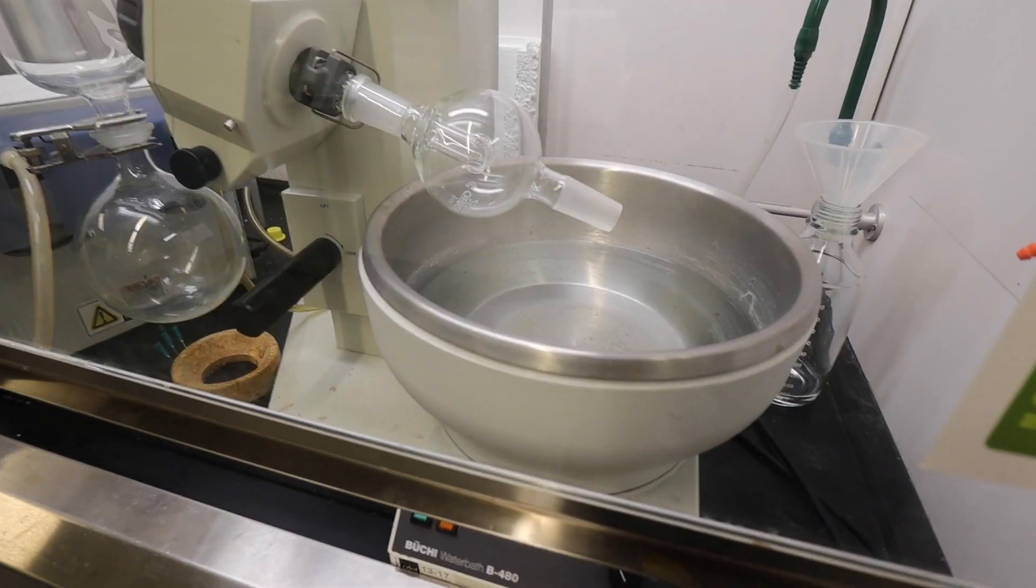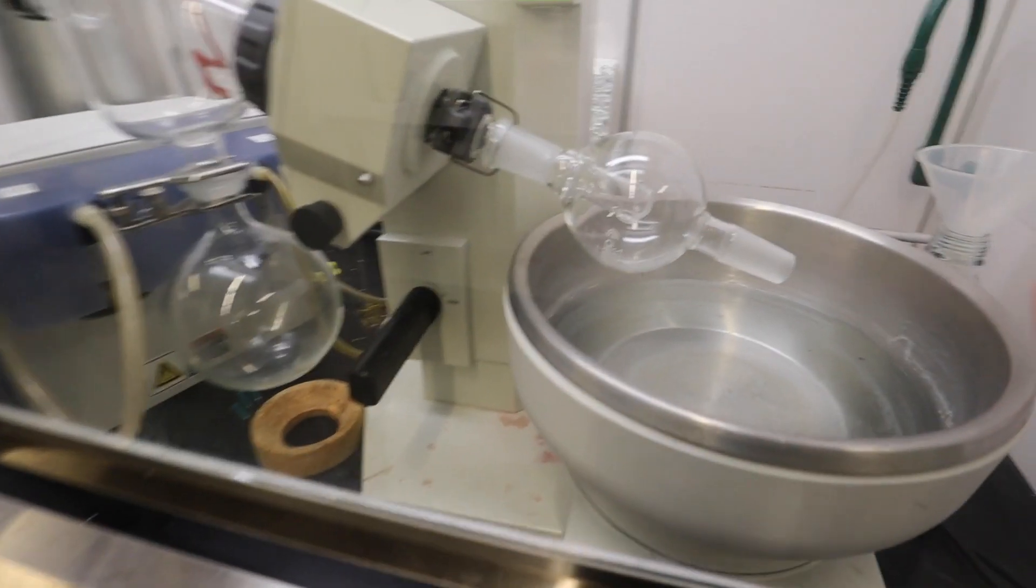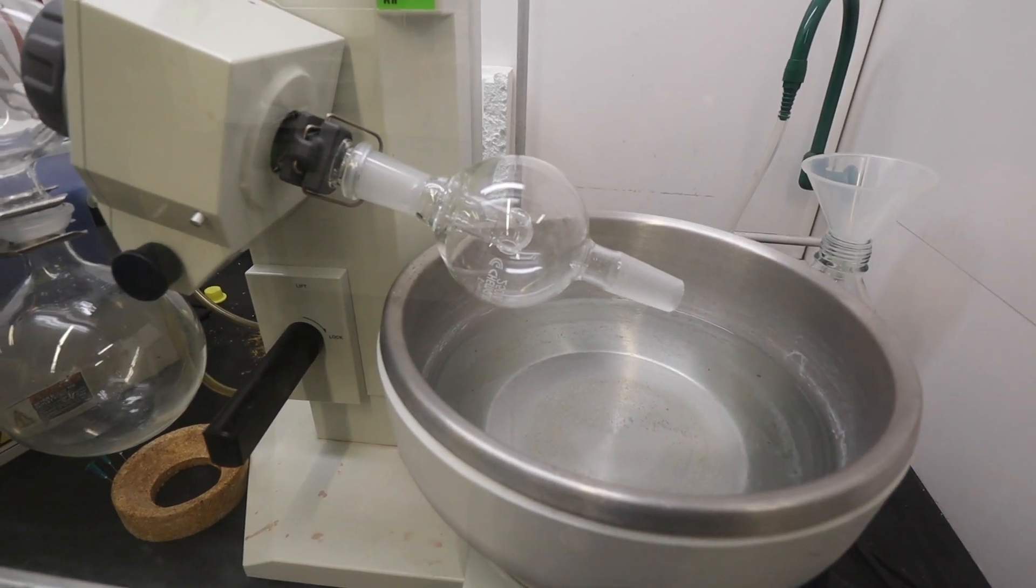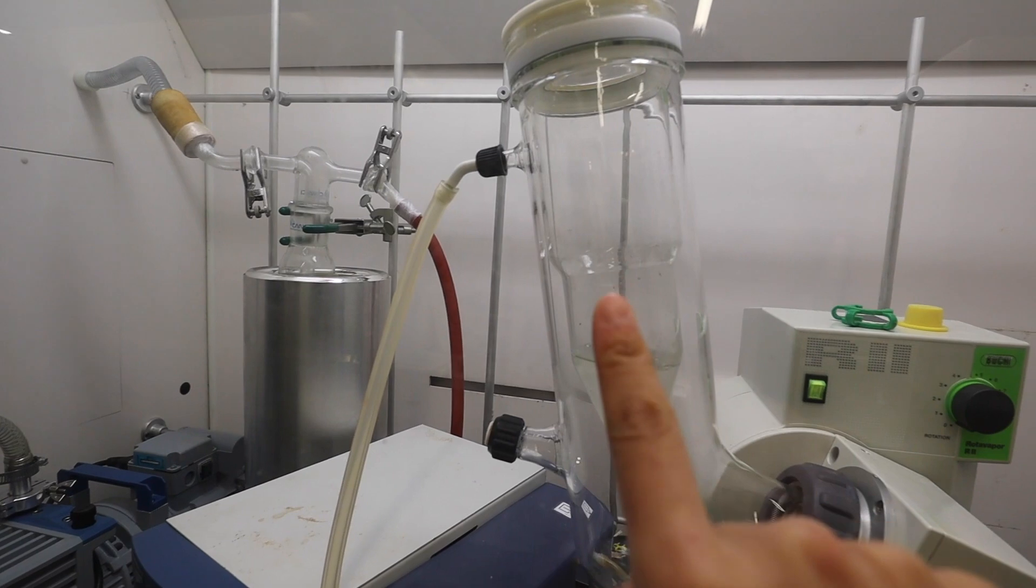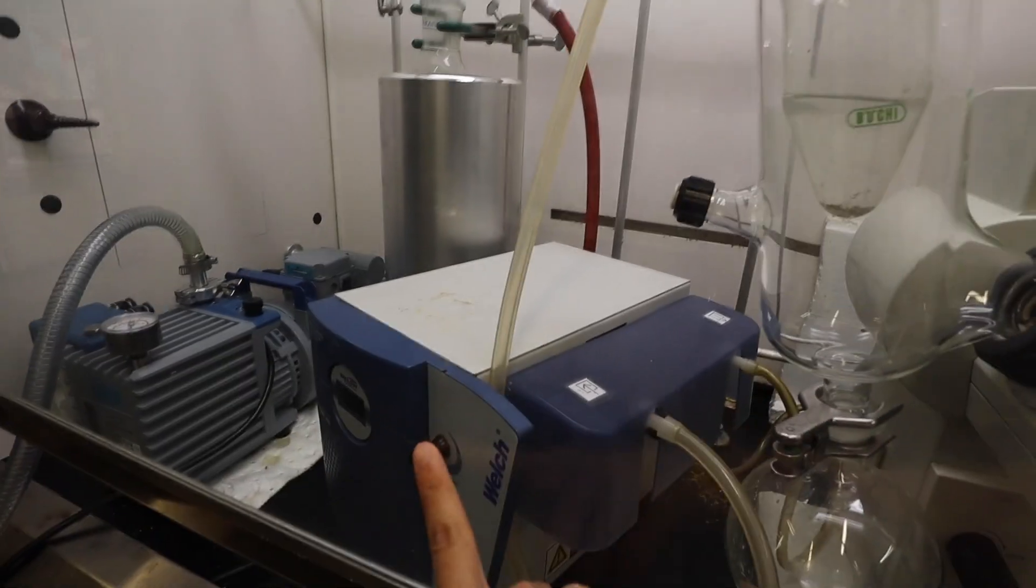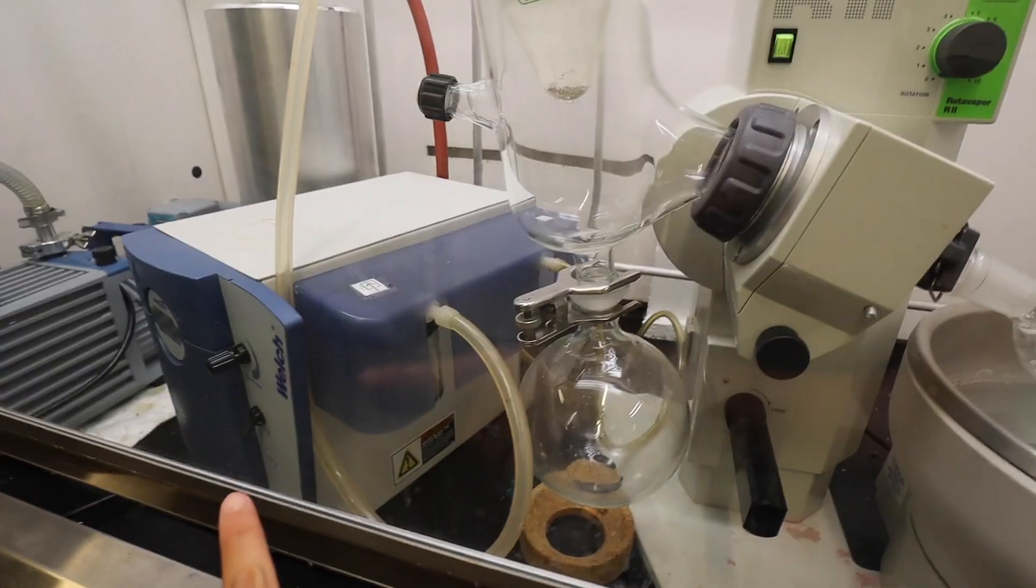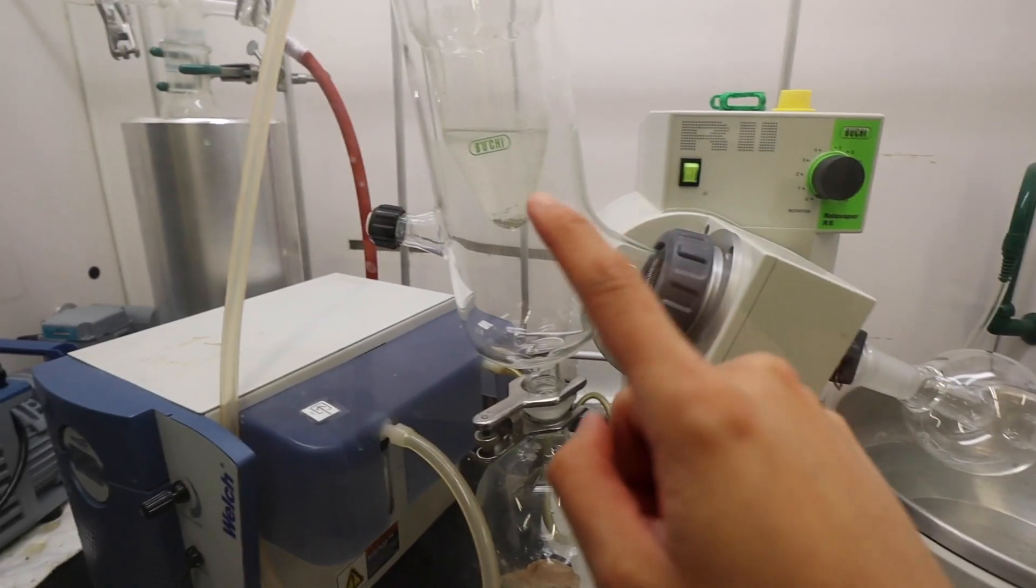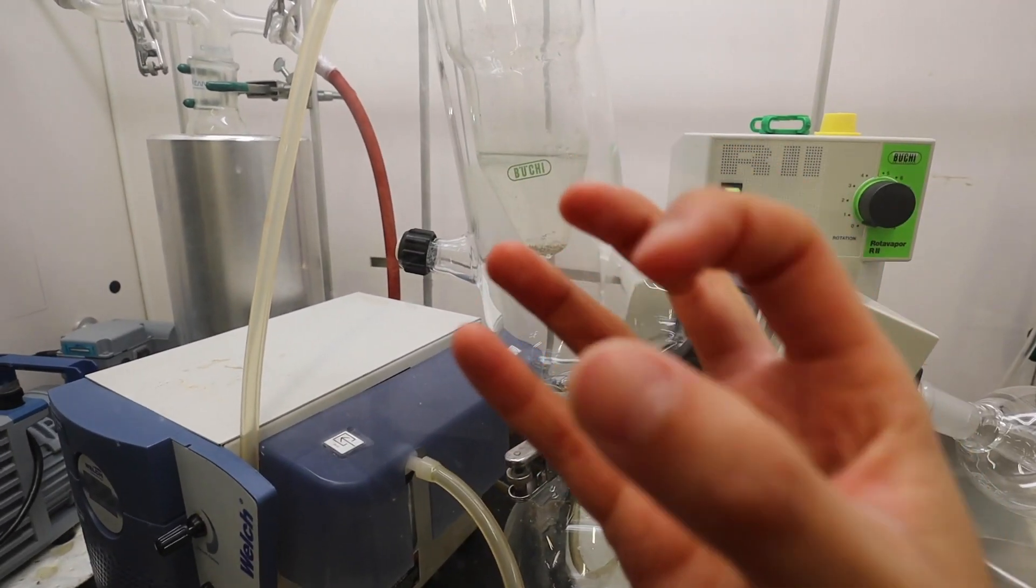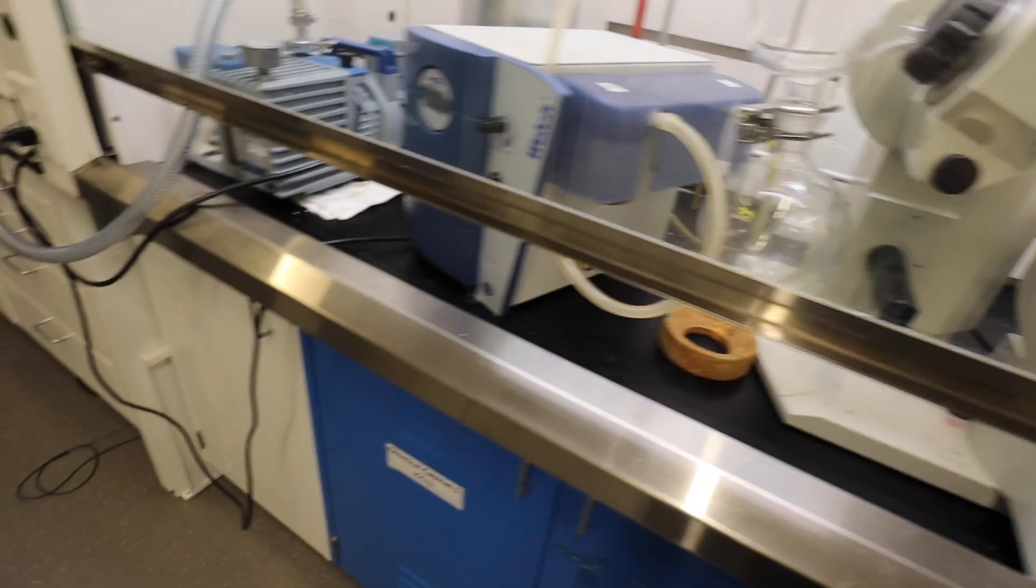So this instrument is used to evaporate organic solvents. So you just put the solvent solution in a round bottom flask here, connect it to this connector, and this is where the dry ice goes to make it really cold. This is the pump which is connected to it and basically with the heat and the vacuum the solvent evaporates. The condensate goes through here and the dry ice will turn it into a liquid again and then it will come down and collect here.